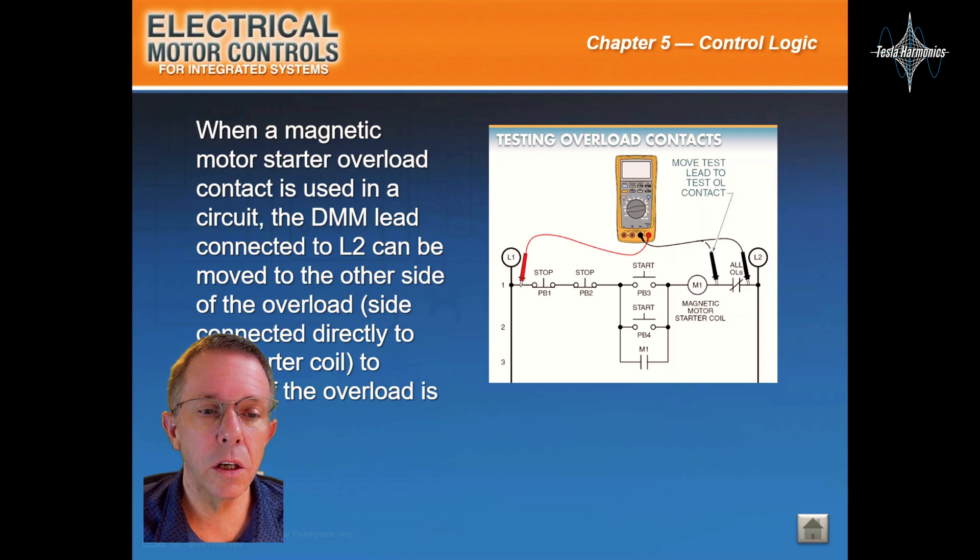When a magnetic motor starter overload contact is used in a circuit, the digital multimeter lead connected to line 2 can be moved to the other side of the overload or the side connected directly to the starter coil to check if the overload is open.